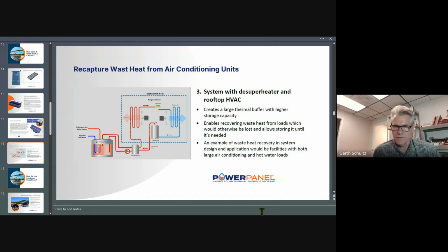Sure. In an air conditioning system, the cold benefit you feel coming out of the HVAC system, the cold air blowing in, is because energy has been extracted and withdrawn from that building. In a refrigeration cycle, there's a hot side on that element. The refrigerant is quite hot, and there's a device that can be put into that hot fluid stream so that water, or a working fluid, can be circulated to extract that heat, in case you have domestic hot water heating purposes or other thermal purposes within your building.